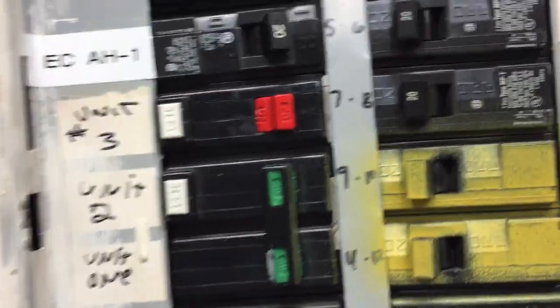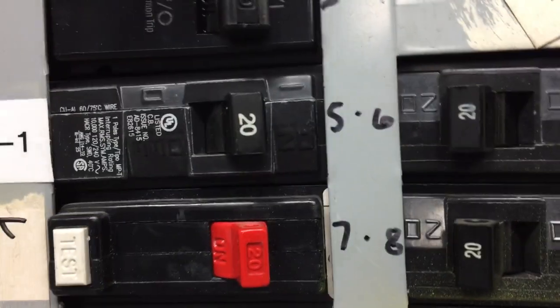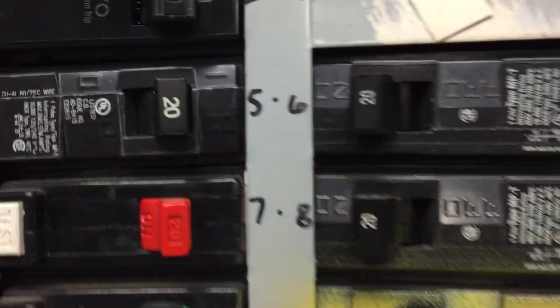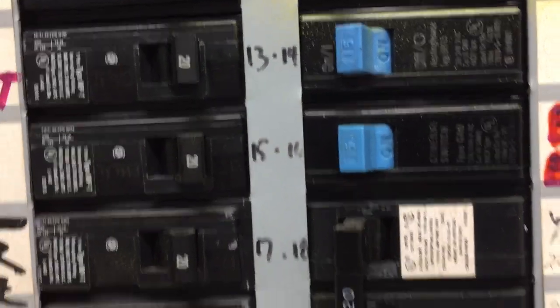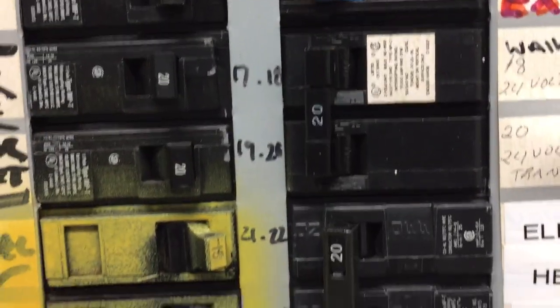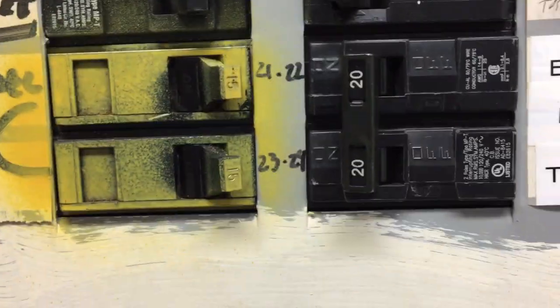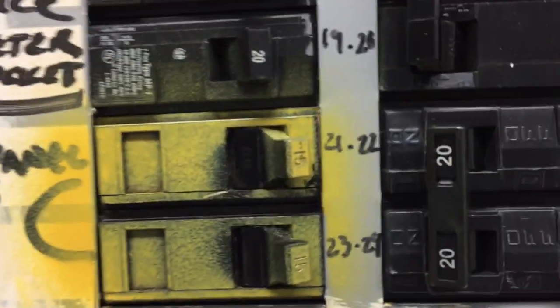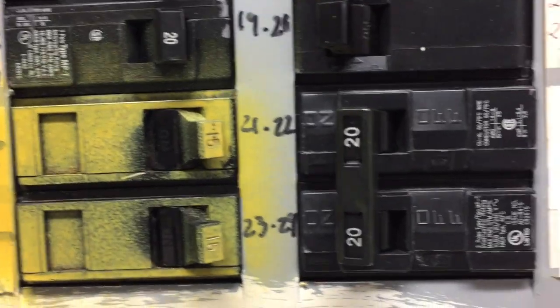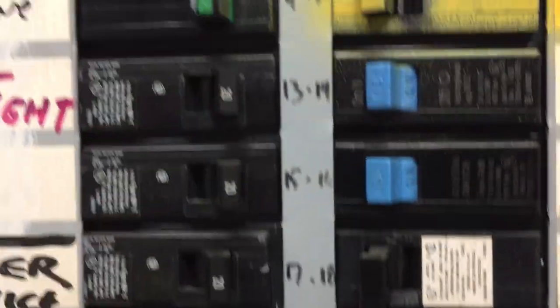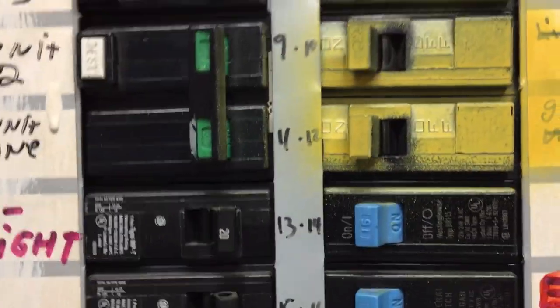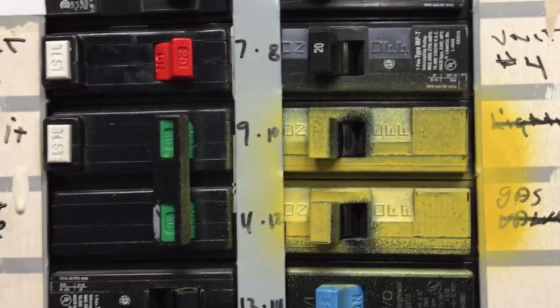Also you'll notice there are several different brands of manufacturers in this panel board and so that might be a violation of section 110.3B. Equipment has to be installed in accordance with instructions included with the listing.